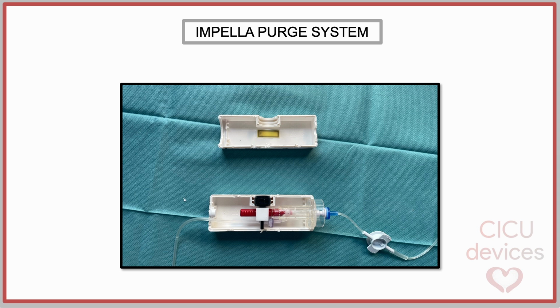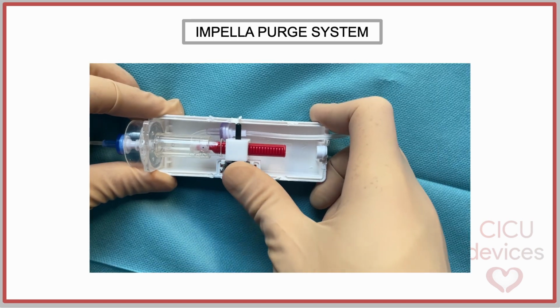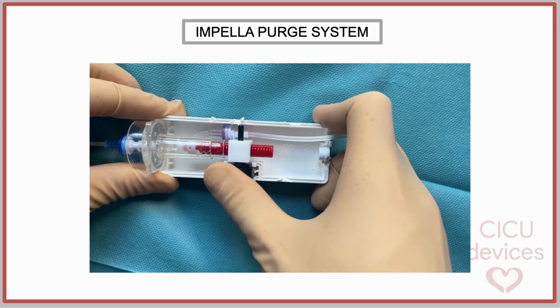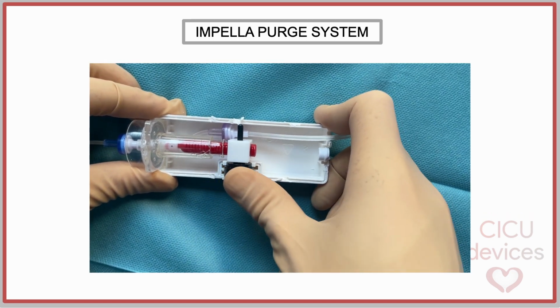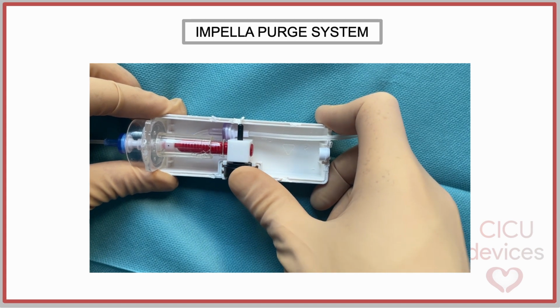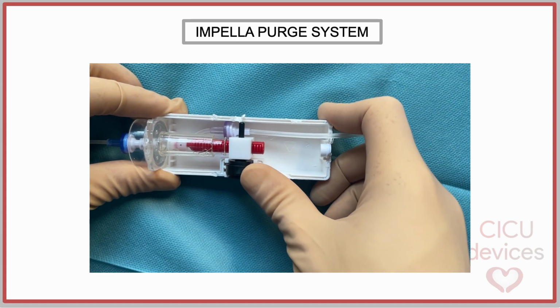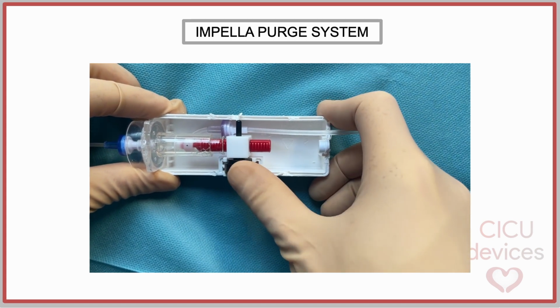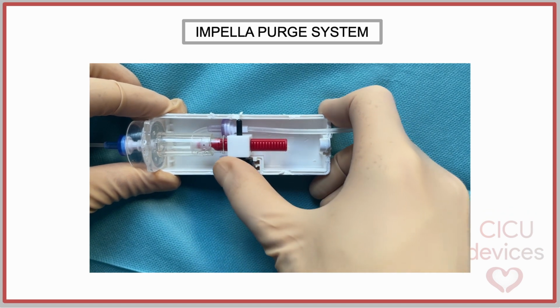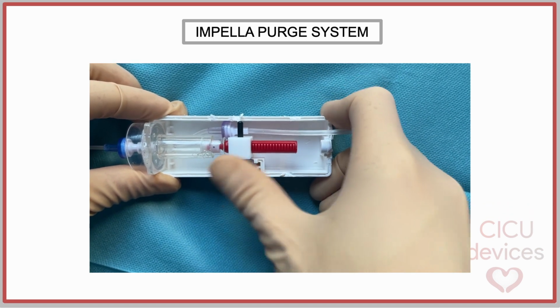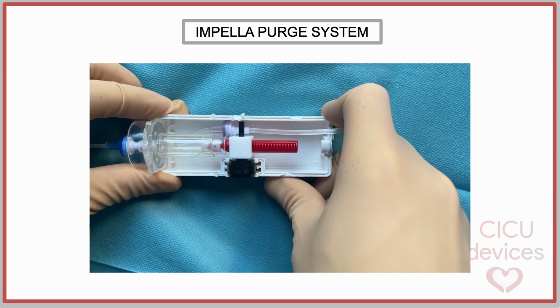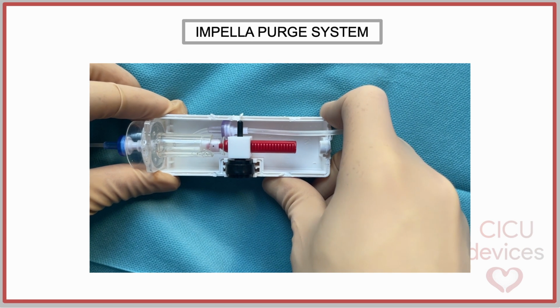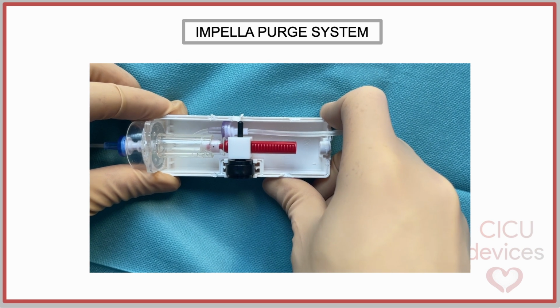The Purge Cassette of the Impella device incorporates a rack-and-pinion piston pump mechanism integrated with two unidirectional check valves to precisely regulate purge flow and pressure within the system. This electromechanically driven positive displacement pump features a linear piston coupled to a rack gear, which is actuated by a pinion driven by the stepper motor in the controller.